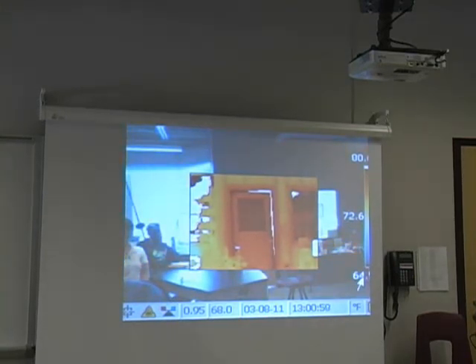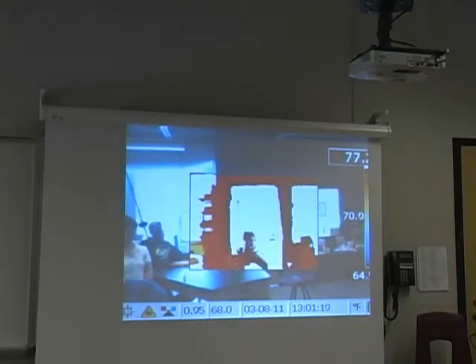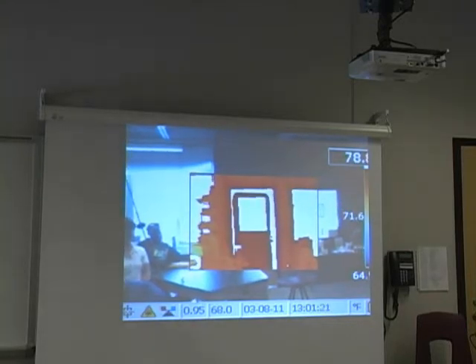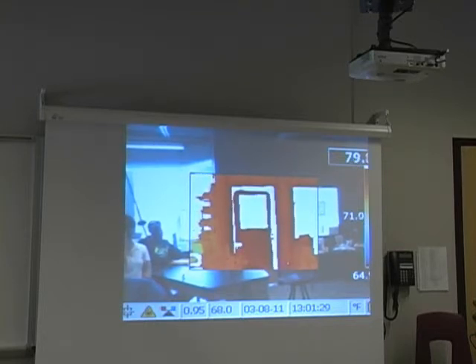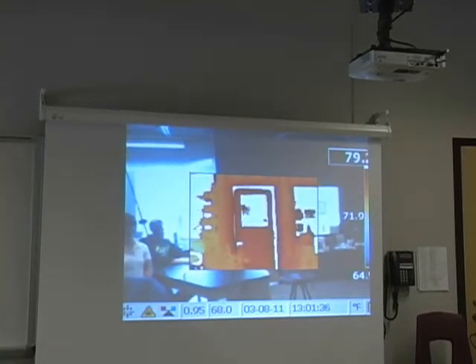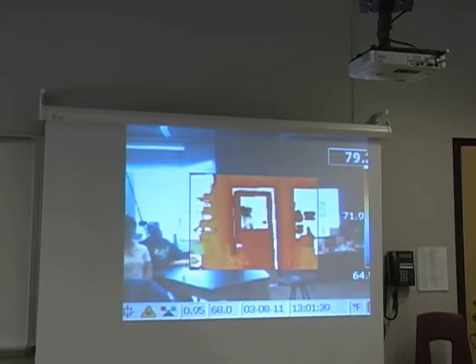And no adjusting that. So as we tighten it, before you couldn't see any difference around that door whatsoever. Now it looks like, well, there's some heat coming out of that door. I come over here and tighten this up a little bit more. Too far. Now that whole door is hot. You've got to change that door as well. You can make that door look anything you want it to look like. And you can start making it look a little more normal. You can do that with just about anything. If I go the other way with this thing, over this.